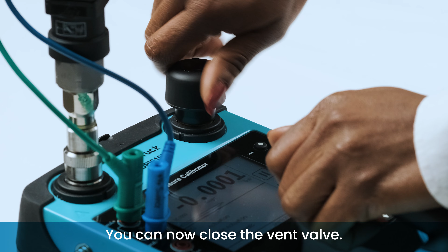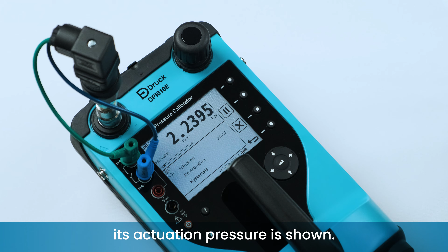The switch I have here is rated to trip at 2.5 bar, so I'll pump up until about 2 bar, then use the volume adjuster to slow down the pressure generated. When the trip pressure is reached, its actuation pressure is shown.